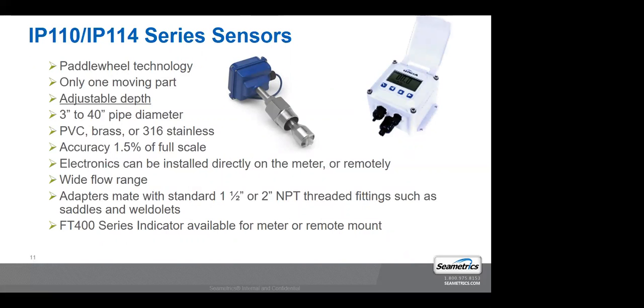There are paddle wheel meters, and we have a paddle wheel meter here on display. These are a pretty popular meter as well. Again, a little less accurate, very economical. We sell a lot of those paddle wheel meters. They only have one moving part, and the bearing is a ruby jewel bearing. They're really durable. If it ever needs to be replaced, it pops out, pops back in. So paddle wheel meters are also a good option, but they're not as accurate as an inline meter.